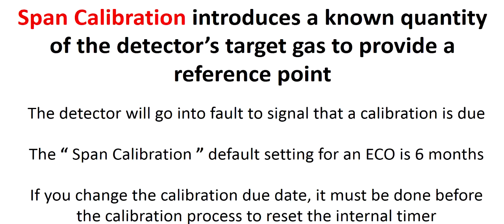Span calibration introduces a known quantity of the detector's target gas to provide a reference point. The detector will go into fault to signal that a calibration is due. The factory calibration due date can be set between 1 and 12 months with a factory default setting of 6 months. Facility specific environmental conditions can affect the calibration period time frame. If you want to change the calibration due date, the change needs to be done before the calibration process to reset the internal timer.